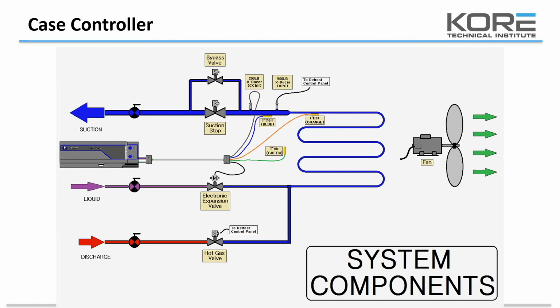So are the orange sensors getting used in just specific cases now? Right, the orange sensor has always been for us to use for defrost termination temperatures, and so that's why they've only been added to the beer cave and the freezer. They're the only ones that have electric assist defrost to add heat to the coil. Your other coils are just an air defrost, and we have not been adding defrost termination to those. We've been allowing them to go on a timed defrost.